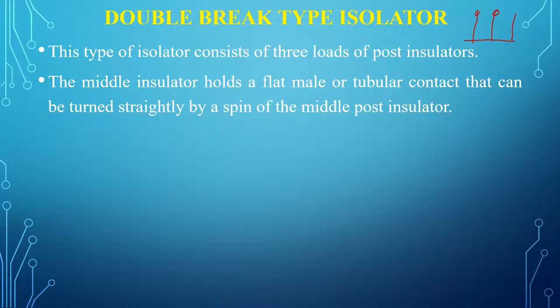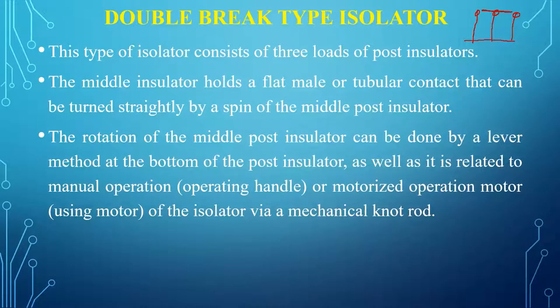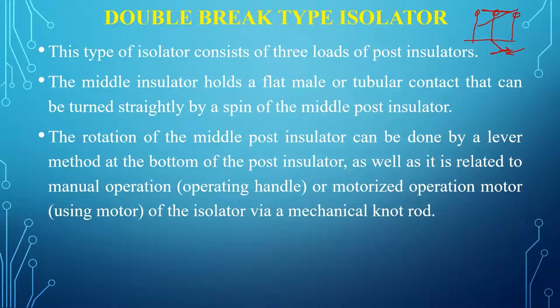The center post insulator holds the tubular contact. There are three post insulators; the center one holds the tube. The rotation of the middle post insulator is done by a lever mechanism. When the lever is pushed one way the isolator opens; when pushed the other way it closes.